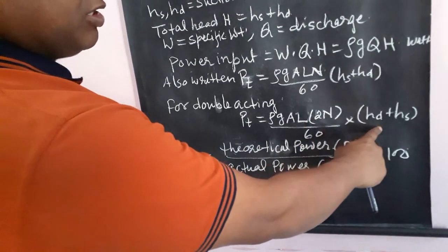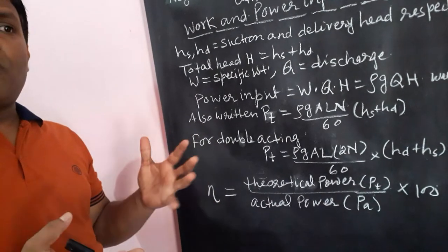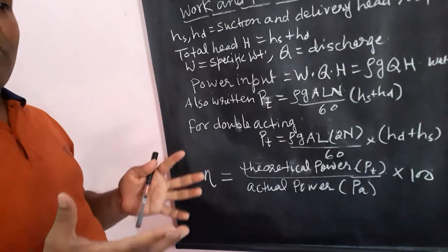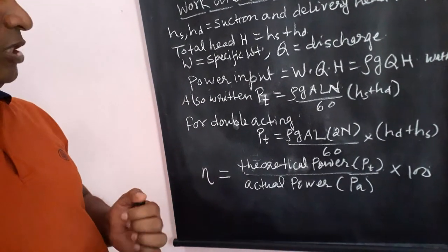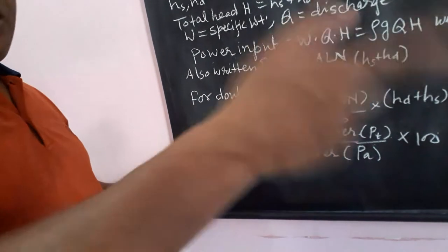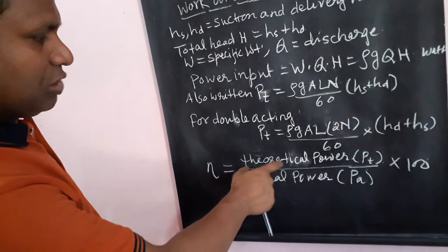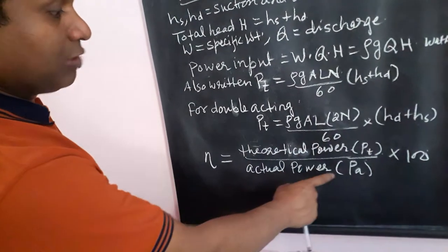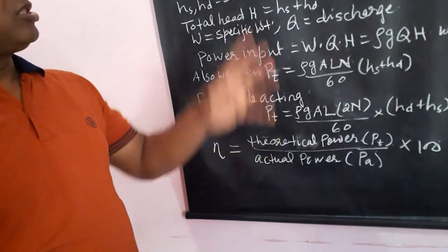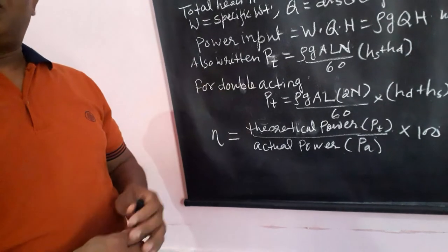For a double acting pump, the theoretical power becomes ρ×g×(2A×L×N/60)×(H_S + H_D). Theoretical power is always less than actual power, where actual power is the power required to run the reciprocating pump. The efficiency of the reciprocating pump is: efficiency = (theoretical power / actual power) × 100.